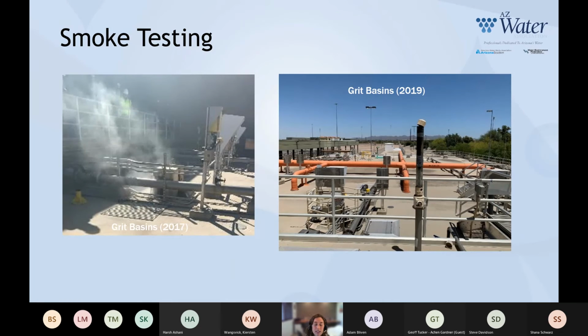And then this is the grit basins when we dropped the smoke bomb into the fine screen influent channel. This entire grit basin area had some smoke pouring out right on the upstream side of it. But now you can see there was no smoke migration at all.